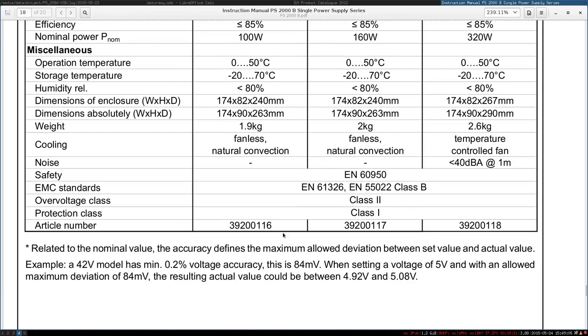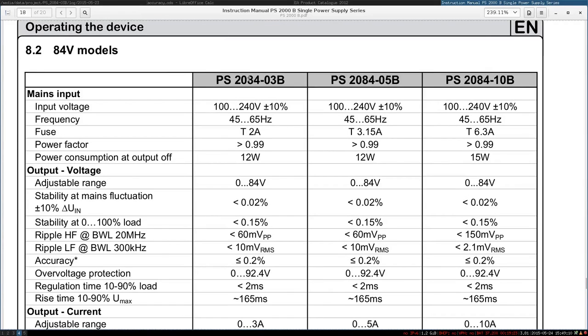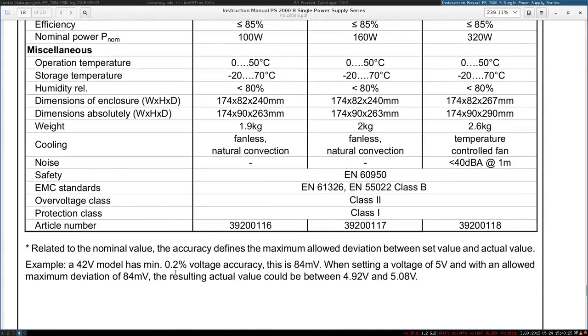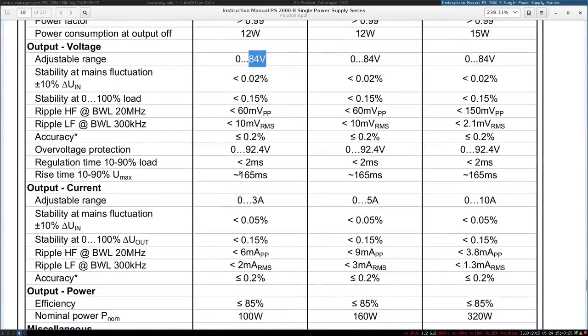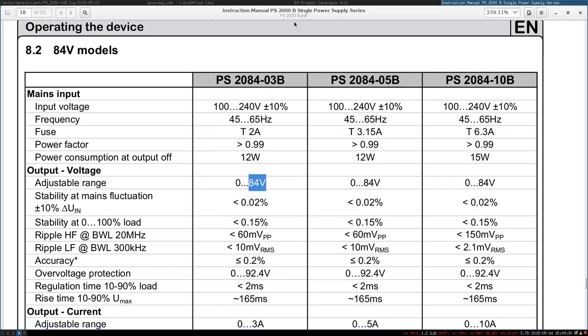So this is related to the nominal value, and the nominal value is the maximum value. The maximum value here is 84 volts. So the accuracy should always be less or equal than 0.2% of 84 volts, and that's around 160 millivolts, around 170 even if you round it.